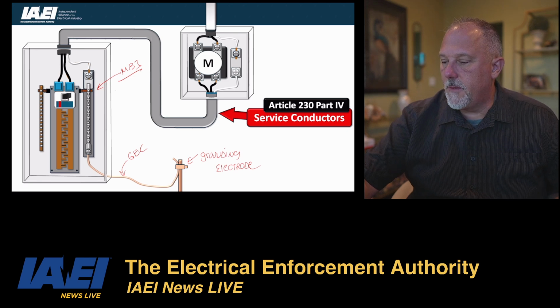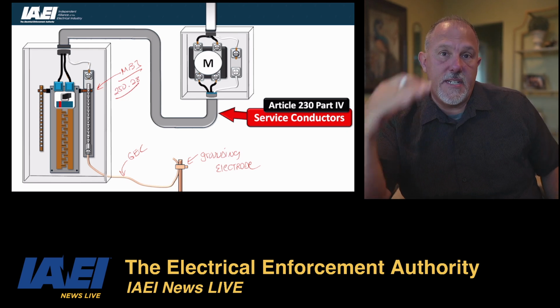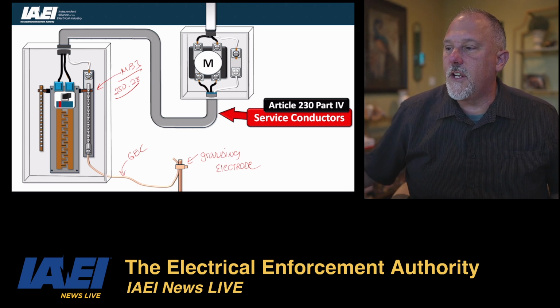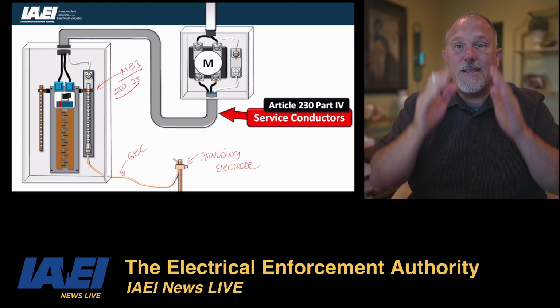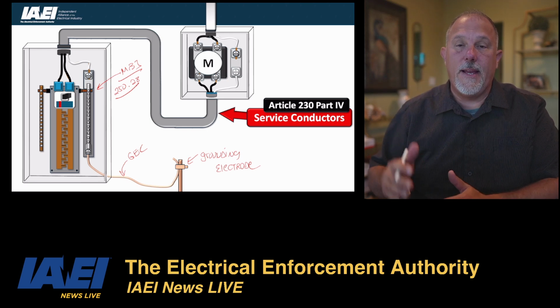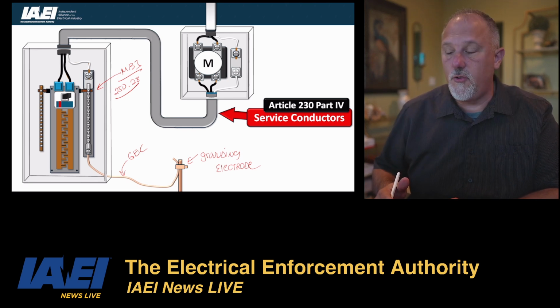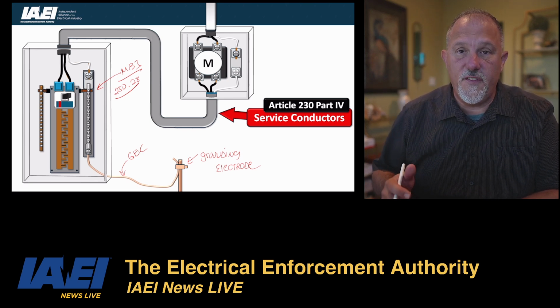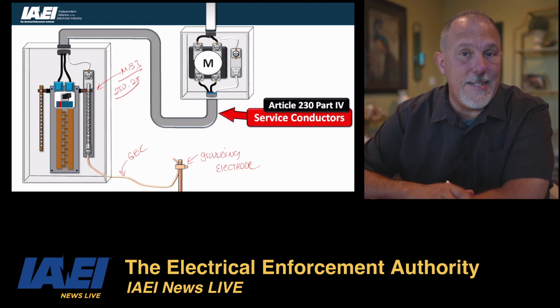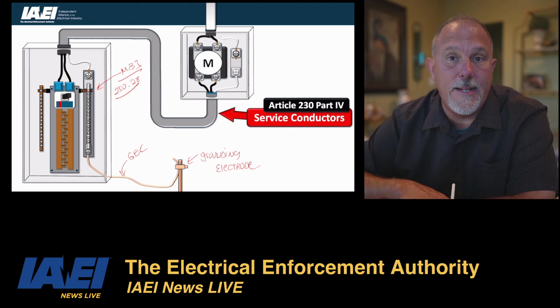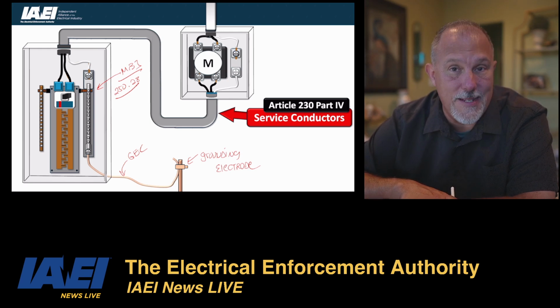So the main bonding jumper is 250.28. This is going to tell you the material that it can be made out of, the construction, the attachment, how to size the main bonding jumper. If you bought listed equipment that is suitable for use as service equipment or suitable only for use as service equipment, those details are all taken care of for you. And service equipment is required to be listed.